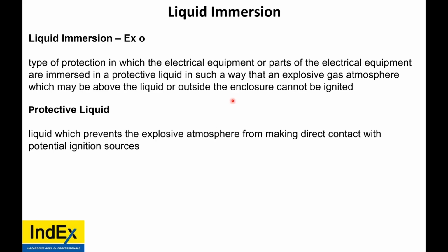Okay, liquid immersion. Well, liquid immersion in Ex o is the type of protection in which the electrical equipment or parts of the equipment are immersed in a protective liquid in a way where an explosive gas atmosphere, which may be above or outside the enclosure, cannot be ignited. So it's excluding the gas from being near the terminations, the bus bars within the transformer. Now, the protective liquid prevents, once again, it from making contact with potential ignition sources. So potential ignition sources: heat, arcs, sparks.